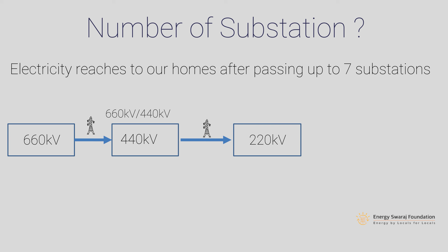So in most cases, the electricity will have to pass through 6 to 7 substations before you use it. The highest voltage in many countries is about 660 kV or 660,000 volt. Then you need to transmit it, and there is a substation which will convert 660 kV to 440 kV. Then you need to transmit and convert into 220 kV. Then again you need to transmit hundreds of kilometers, and convert into 110 kV. Then from 110 kV to 66 kV. All these stages require, by the way, transformers. So there are lots of transformers sitting in between. Then from 66 kV to 33 kV. From 33 kV or 33,000 volt to 11 kV, 11,000 volt. And then finally 230 volt.